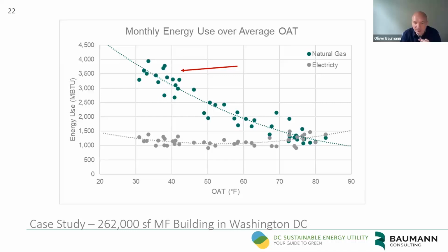The gray dots is the electricity consumption, again, monthly over the outdoor air temperature. We don't see much impact of the outdoor air temperature here, but we do see that in warmer months, 70, 80 degrees, we have a slight increase of the electricity consumption. That is an indication for cooling. Our chiller works with electricity. However, in a well-tuned building, I would like to see a more dominant increase, or I should say I would like to see a lower baseline of the electricity use. So we see that this is almost flat across the year. Also over the 3 years, there is not much change. Again, an indication that there is a lot of opportunity for energy efficiency.